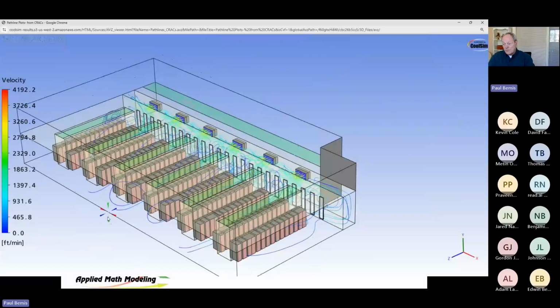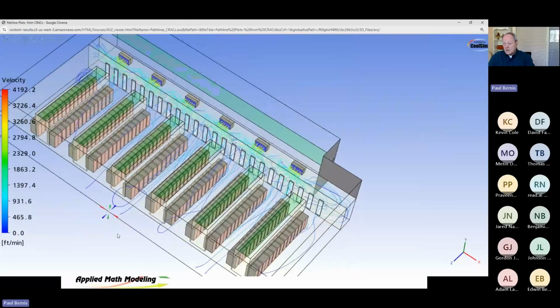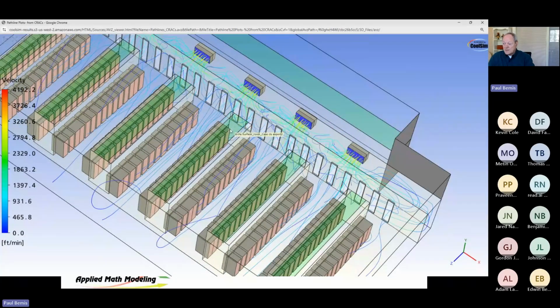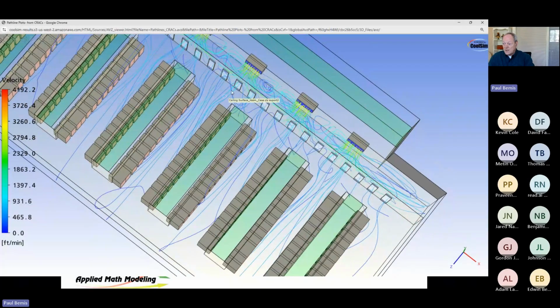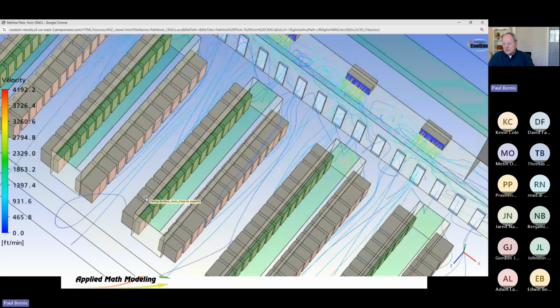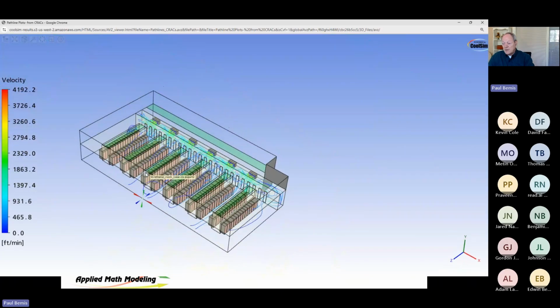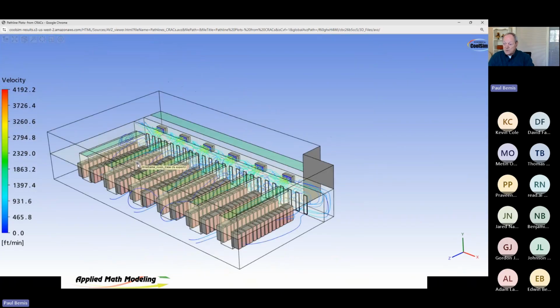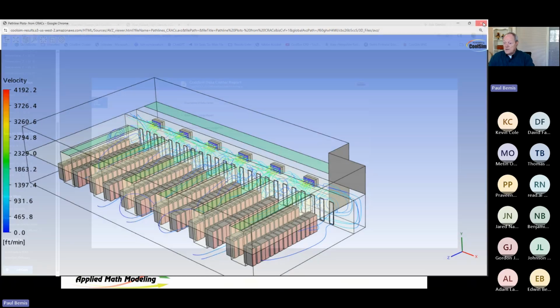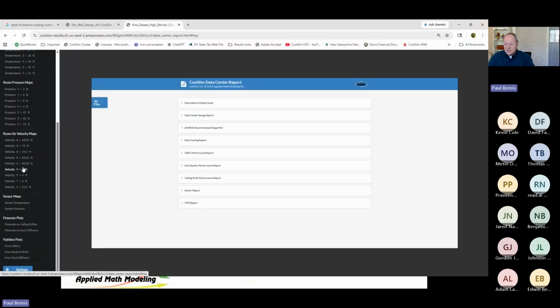This is asymmetrical from an air delivery point of view. You can tell by looking at it. Generally, what you run into here is high velocity along these edges. So right here, you'll have high velocity coming out across, causing leakage to occur on this end. And the problem, therefore, is by the time you get down here, you don't have any air left because it went in here and up into the ceiling, and there's nothing left. So you're leaking up front and you're starving further down the line. Very classical kind of problem. This is how they did them a lot before they went to dual fan walls. And you'll see in this design, of course, we're going to have that same problem with the temperature leaking.